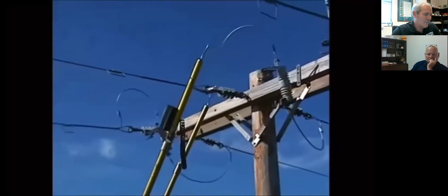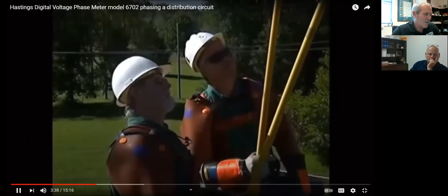On a lot of feeders, when they want to take it off, if you've got small wire coming out of a substation and it's a heavily loaded circuit, and one side of the switch is a large wire pulled to the substation, it's conceivable we can have a fairly high reading on the same phase, but still go together. I've seen 500 and 600 volts on a distribution circuit.